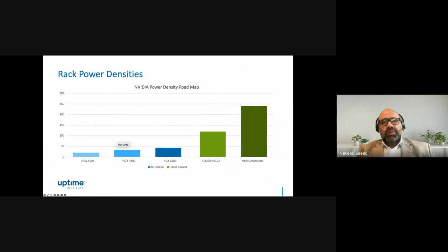NVIDIA's roadmap shows that they are going to have racks up to 250 kilowatts per rack density. On their roadmap, they are already touching 130 kilowatts for now, but they will be moving over and above it in some time. And that is actually the challenge. That's the actual requirement that is pushing the adoption of liquid cooling. NVIDIA is not the only one. Other manufacturers are also heading the same direction.